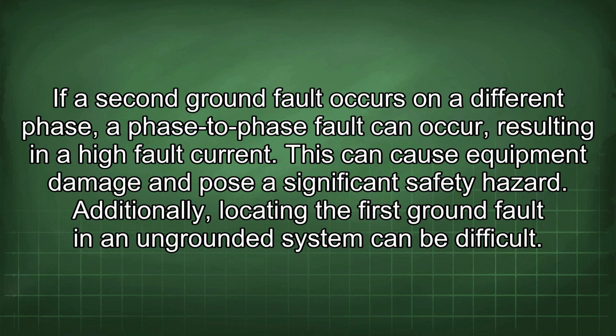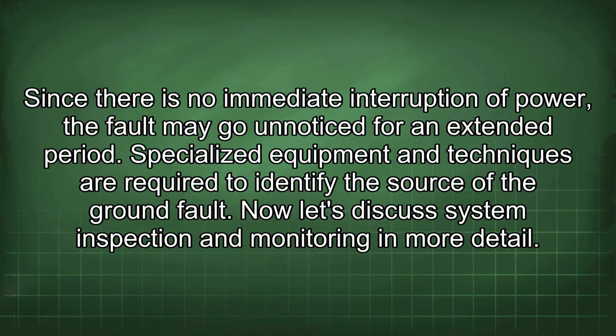Additionally, locating the first ground fault in an ungrounded system can be difficult. Since there is no immediate interruption of power, the fault may go unnoticed for an extended period. Specialized equipment and techniques are required to identify the source of the ground fault. Now let's discuss system inspection and monitoring in more detail.